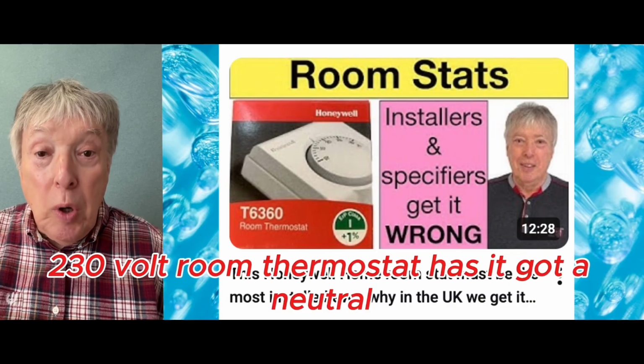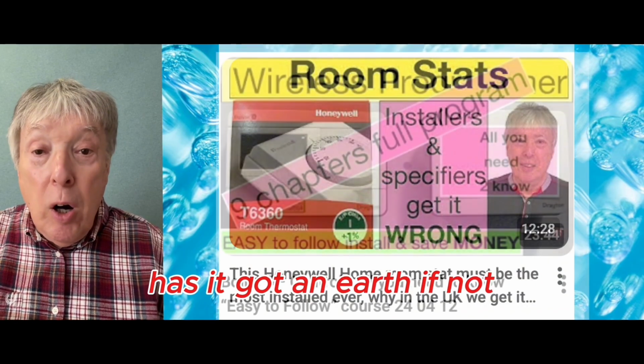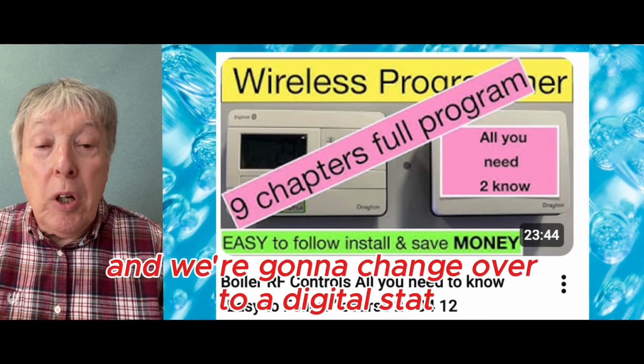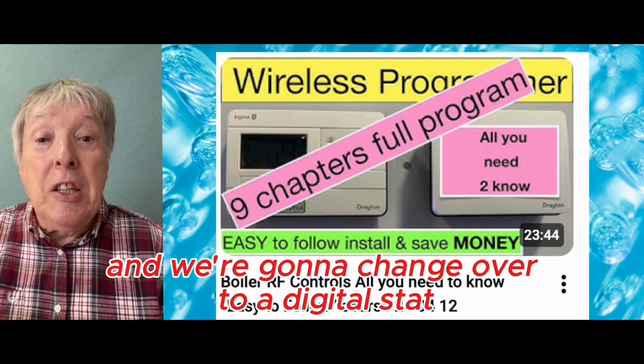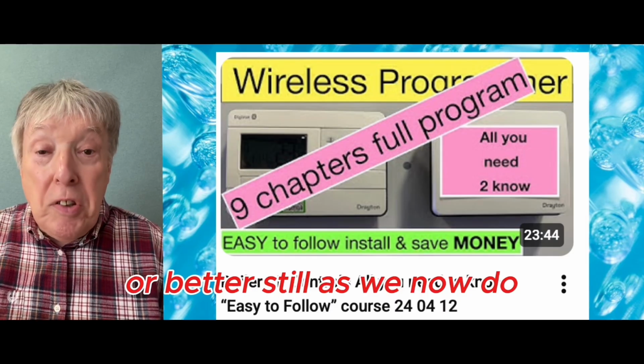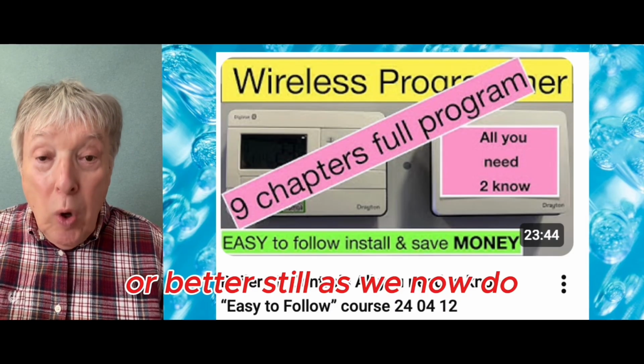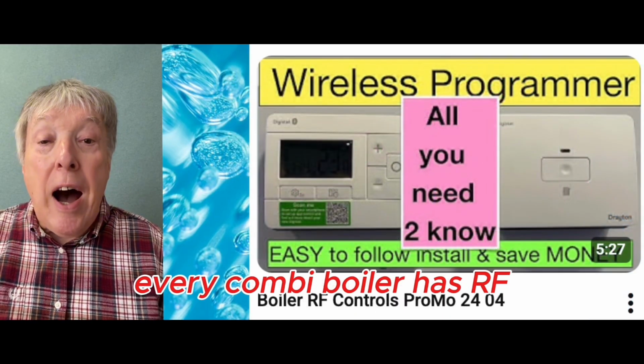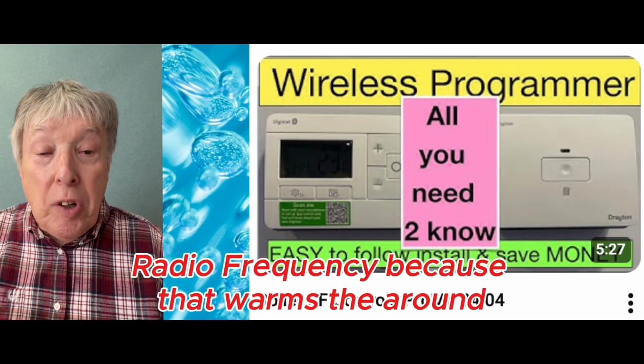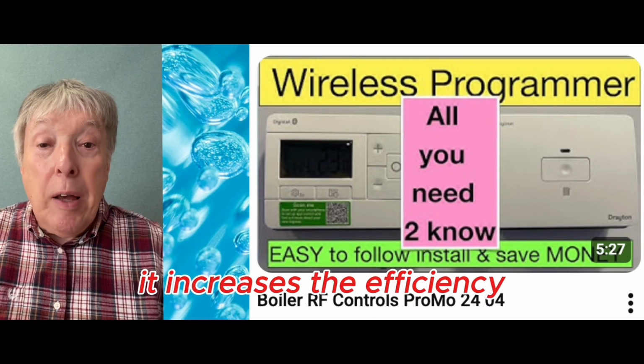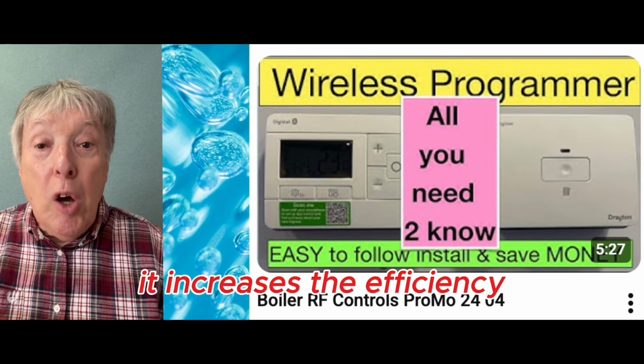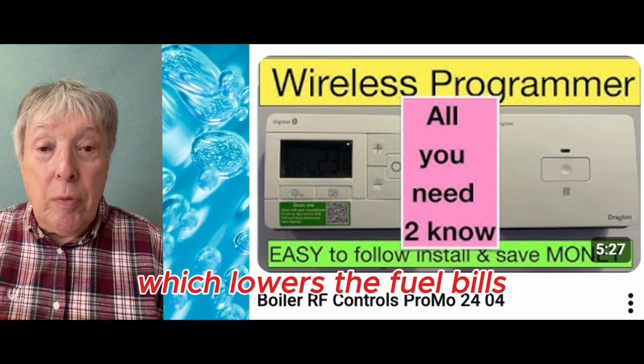Has it got a neutral? Has it got an earth? If not, we're going to condemn it, and we're going to change over to a digital stat. Or better still, as we now do, every Combi boiler has RF, radio frequency, because that warms around. It increases the efficiency, which lowers the fuel bills.